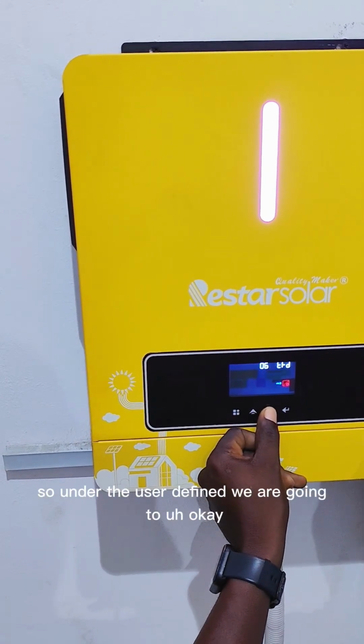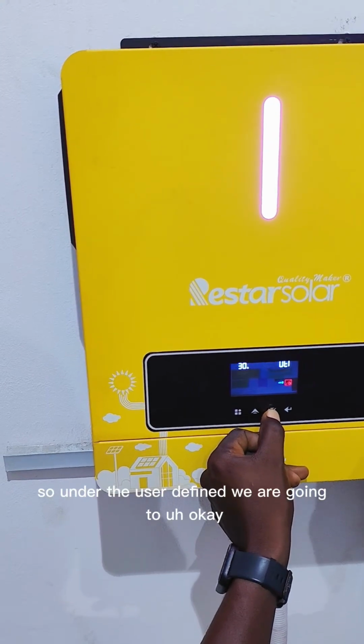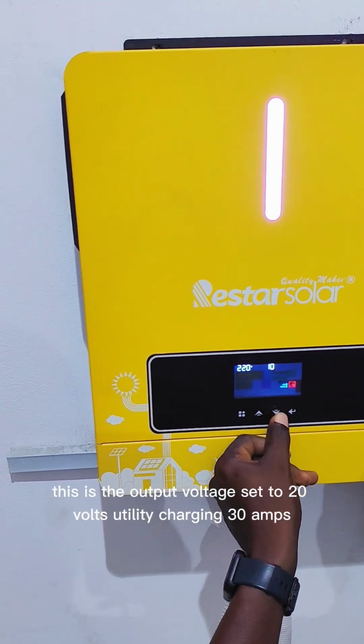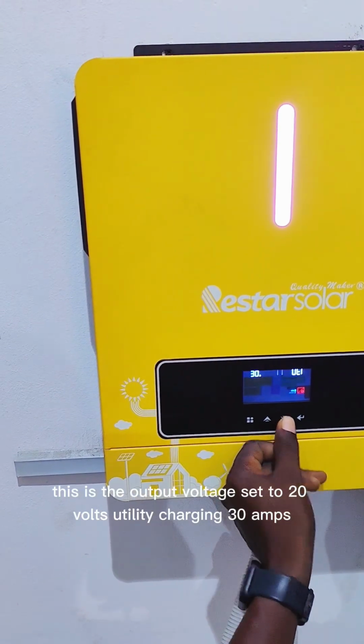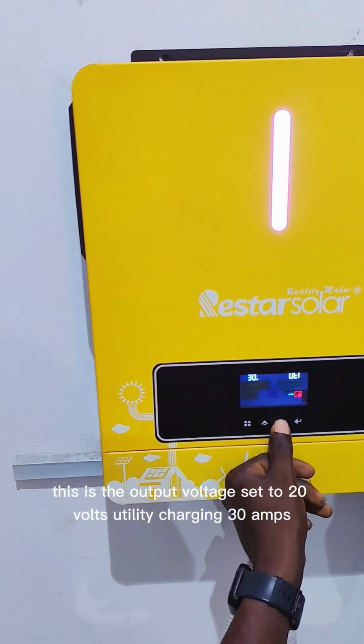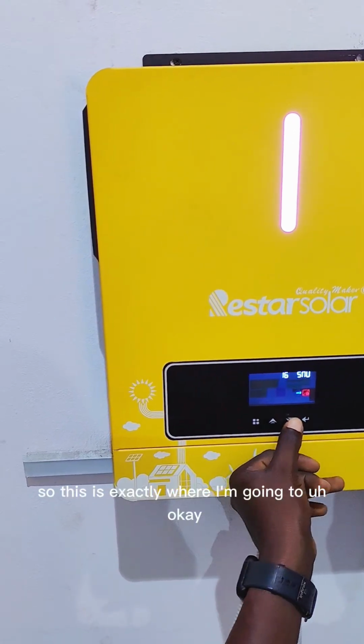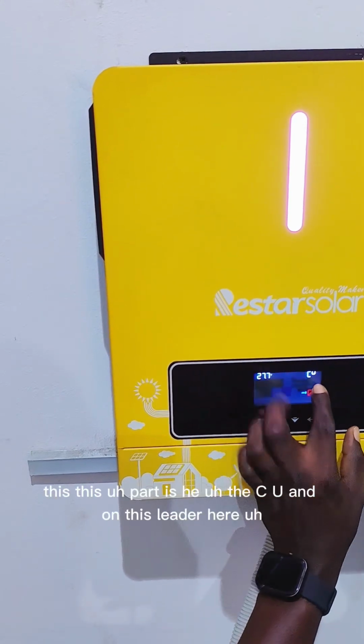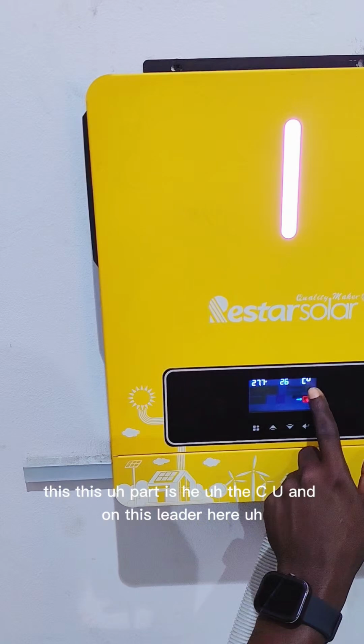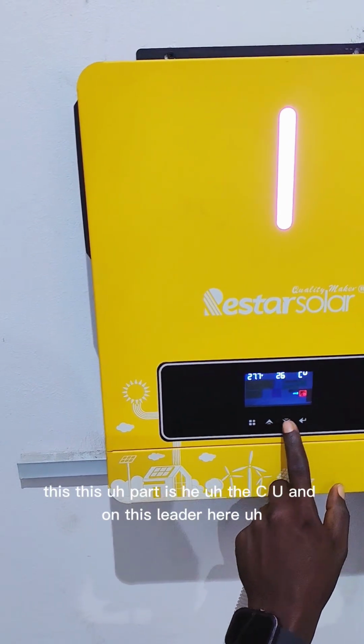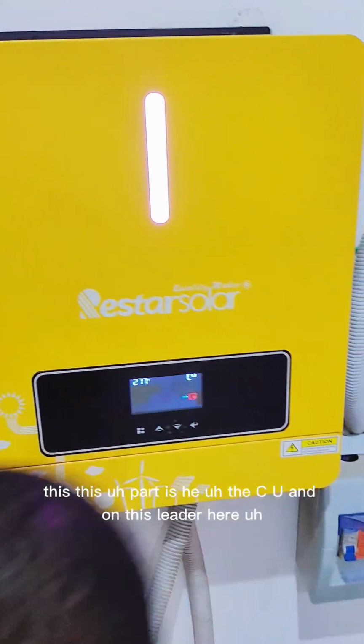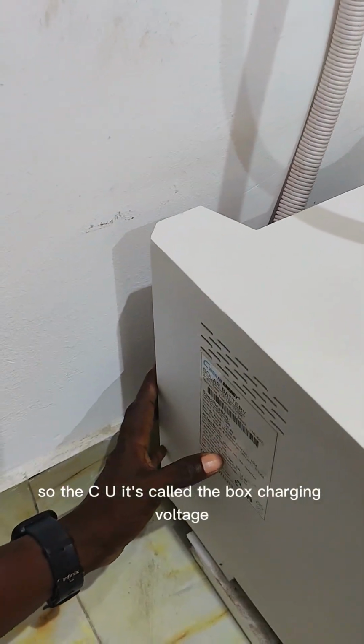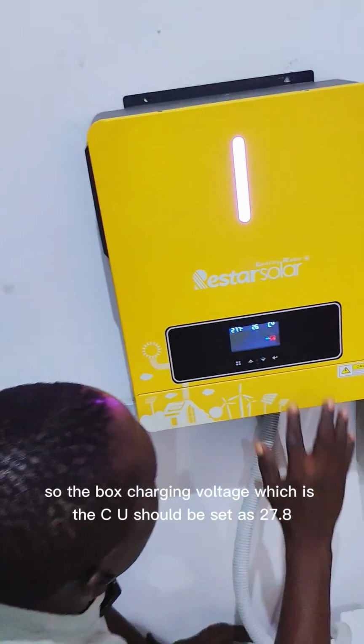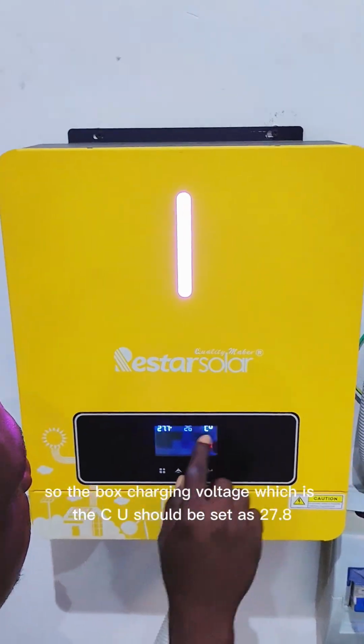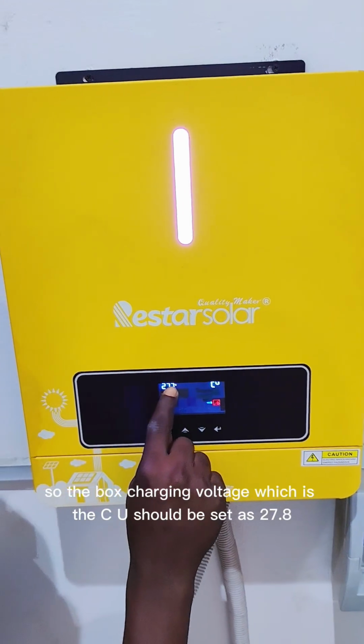So under the user defined, we are going to, okay, this is the output voltage set to 220 volts, utility charging 30 amps. So this is exactly where I'm going to. Okay, this part is the CV, and on this label here, the CV is called the bulk charging voltage. So the bulk charging voltage, which is the CV, should be set as 27.8.